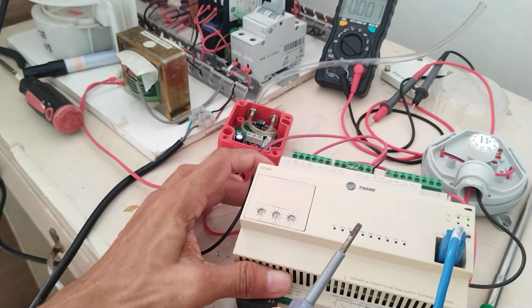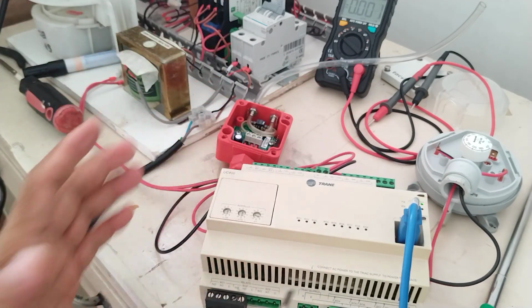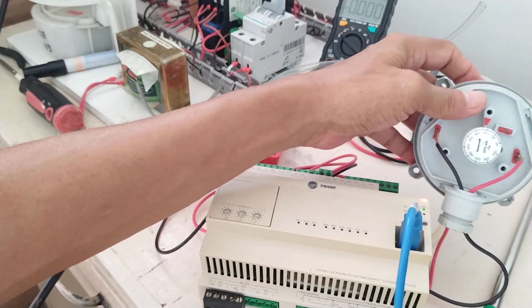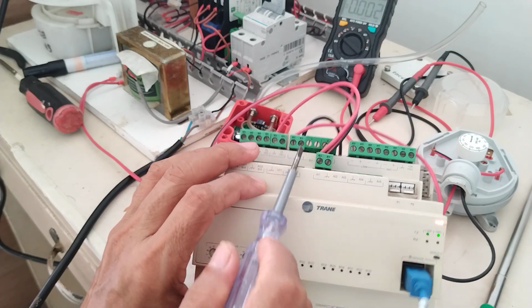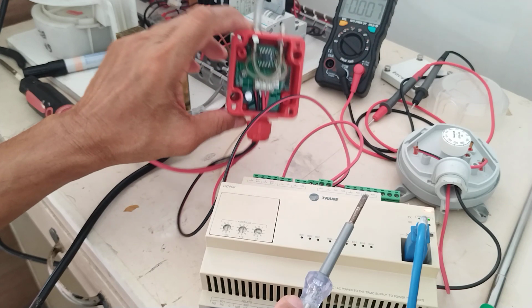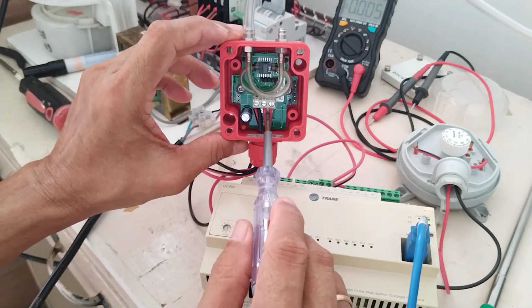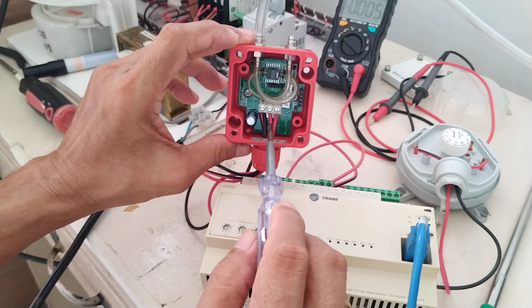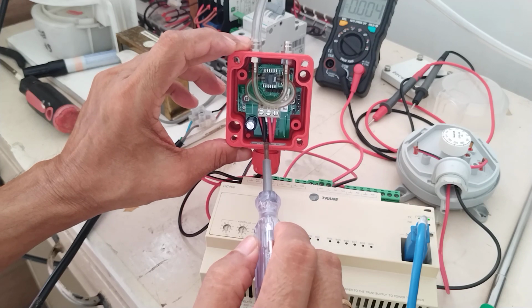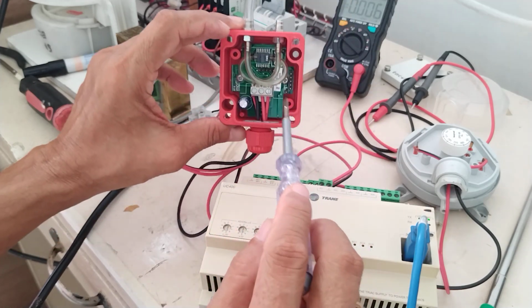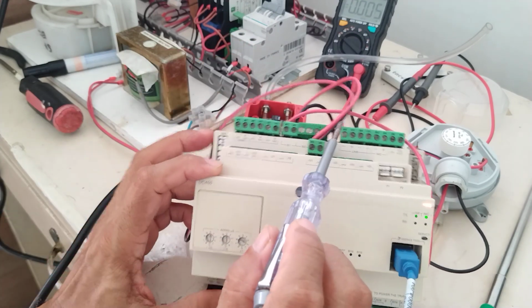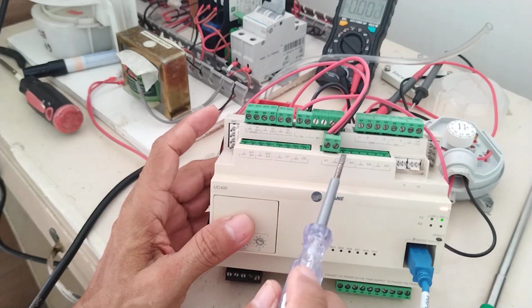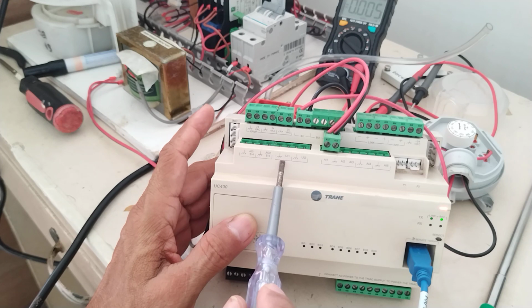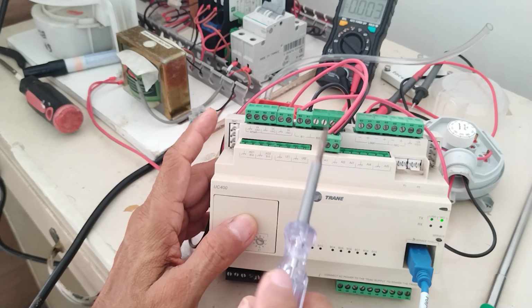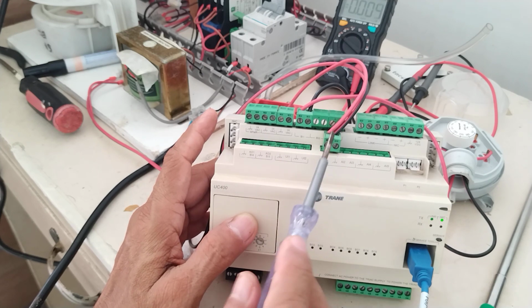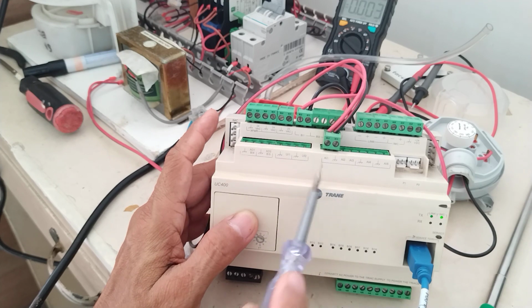Okay, now guys, so what we have done for this tutorial, I have shown you how you will pull cable from field device to the controller for differential pressure switch. Then, for differential pressure transmitter, you need to provide first power. Then, you need to get the output signal of this, which is the current differential pressure as being read by this device. Okay, then how are you going to connect the output signal to your controller? So, you need to use the analog input channel, or you can use also the universal input channel. But again, you need to do some configuration so that you can properly display the value being monitored by this controller.